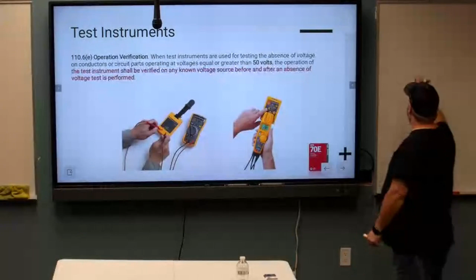So let's say you have two conductors, conductor A and conductor B. Okay. So you have conductor A, and then you have conductor B. Let's say conductor A is energized. Okay. B is not. With me so far? B's not energized. If you take your induction tester to B, it's probably going to say that it's energized. It's going to give you a false reading. And the reason why is because when you energize a cable, it creates induction or a magnetic field around that cable. And some of that induction will transfer over to the other one, giving you a false positive if it's working correctly.